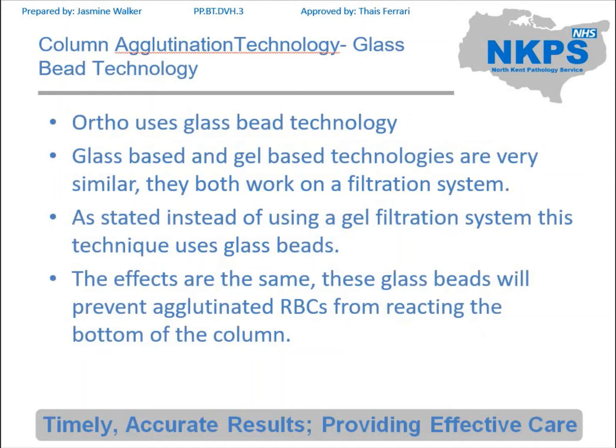Continuing with column agglutination technology, we move into glass bead technology. The main company that uses this is Ortho. Glass beads and the gel-based technologies look pretty much the same. The difference is instead of using a gel there are lots of small glass beads that act as a filter, so again you would end up with a similar result. If there's agglutination the cells won't be able to pass through that glass bead filter; if there's not, they can. These are both very useful techniques that can be performed manually and in an automated fashion and they can do a range of different tests.